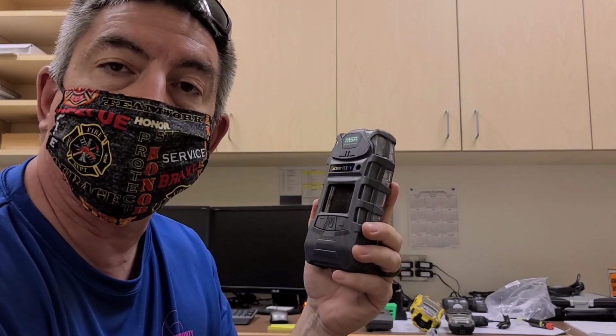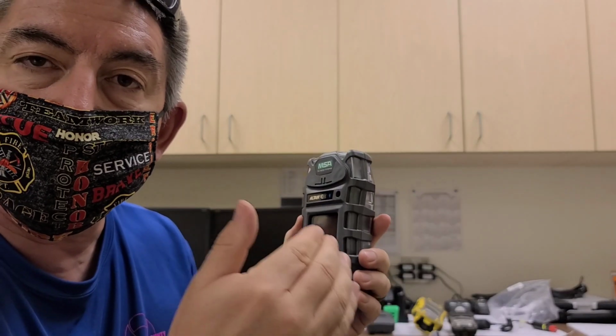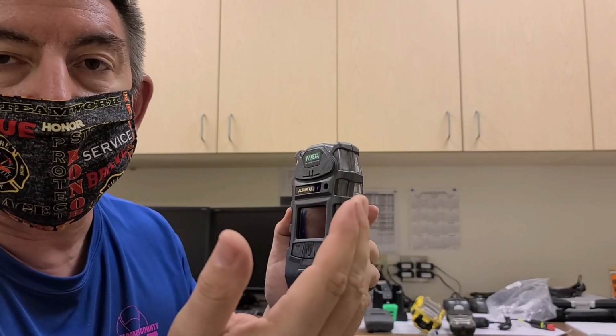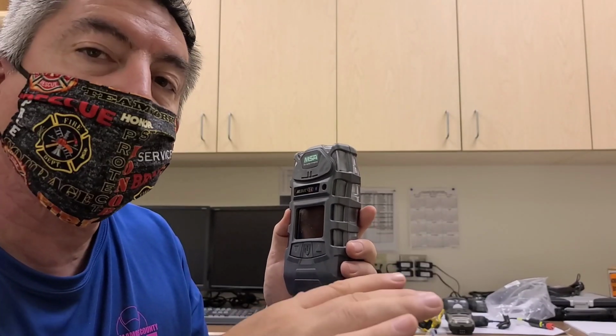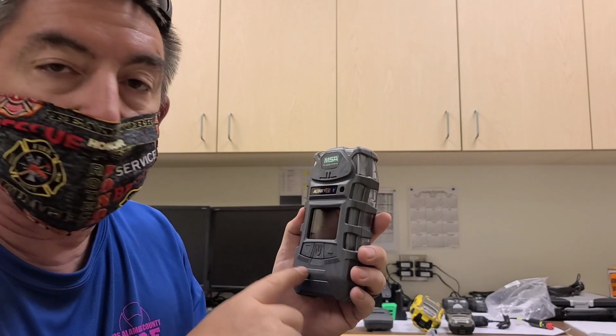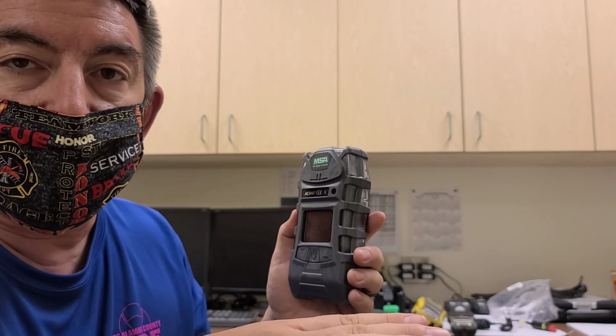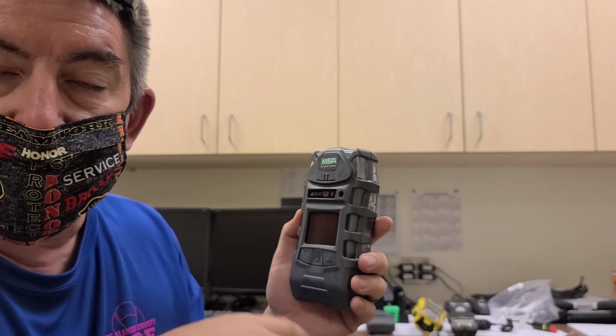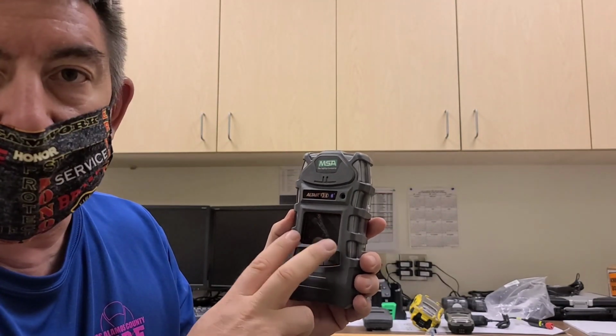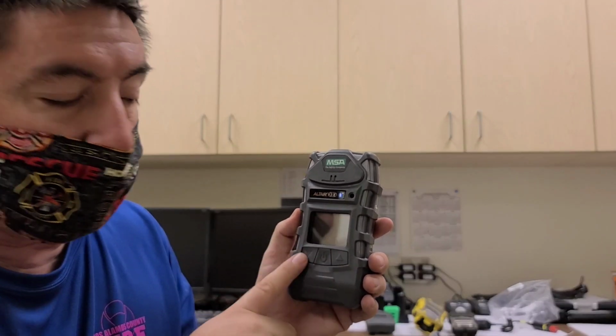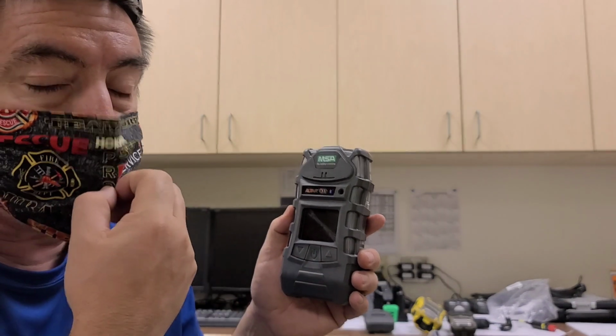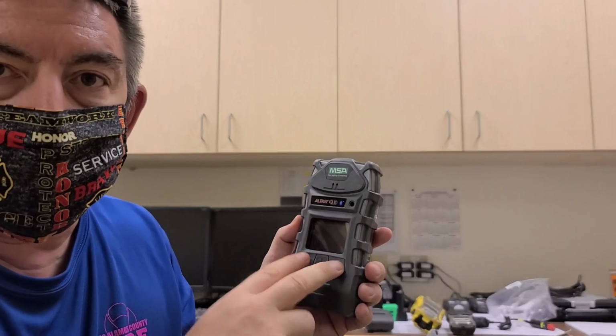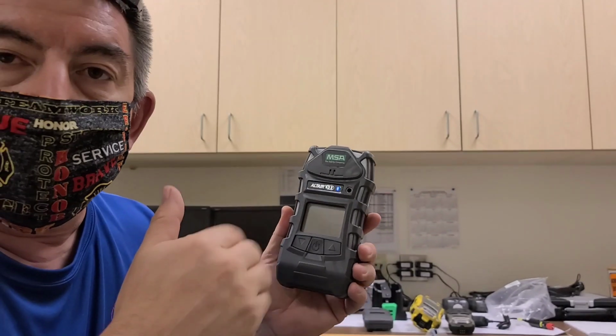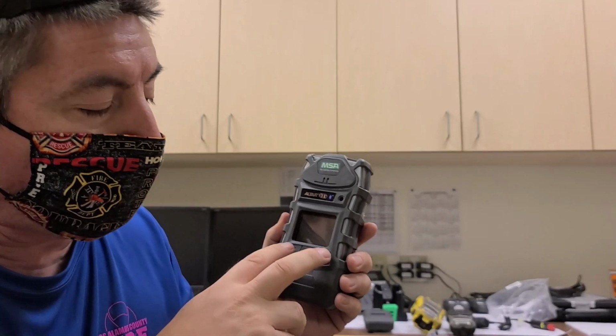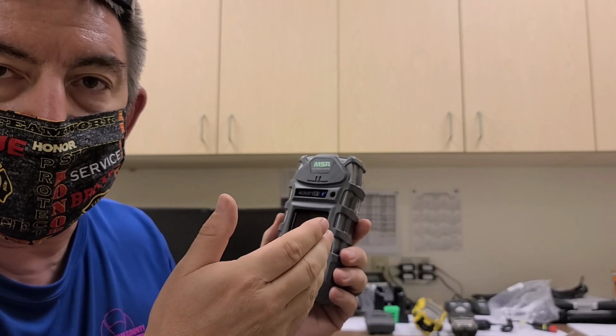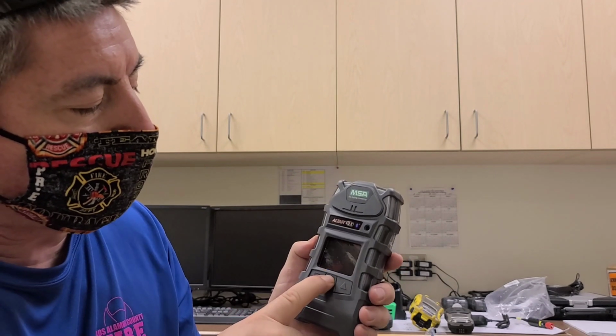So when we start this unit up, you're going to see how it cycles through. It's going to give you your low alarm limits, high alarm limits, and then the option to do a fresh air calibration. You only have 7 or 8 seconds to choose to do the fresh air cal, which only needs to be done on the first day of your tour, or it goes into just the regular measurement mode. After that, the 2 buttons, the down arrow and the up arrow, only show a bump on one side and cal on the other side. You don't have the gases in the field to do either of those, so please do not touch those, otherwise it's going to try to calibrate the machine. It'll turn into an error when it's not able to bump or cal correctly, so we'll have to fix it at that point. It won't be usable.